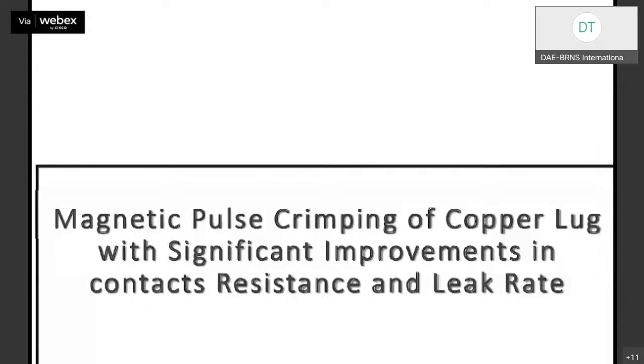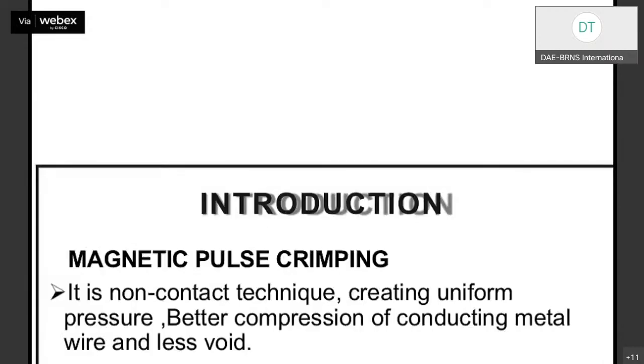Cable is one of the important parts of an electrical system, we can say it is the backbone of any electrical system. So joining of cable, or the end termination of cable, is very important. If the joining is not proper, it can lead to failure of the system, and it has been reported that 60% of failures are due to cable joint failures.